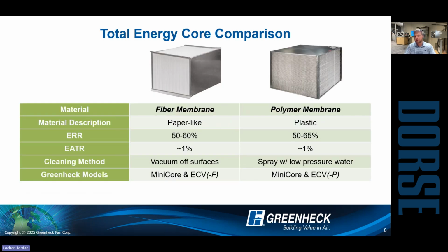On the core side of the market, right? So there's two primary core media types that are out there. A fiber core is a paper-like material, and then a polymer core, very similar to that wheel, is a plastic type media, right? That is a washable and reusable core, right? So you can see the difference there. Cleaning, one is vacuum only, one is low pressure water wash. The big difference being with cores compared to wheels is lower performance, right? So 50 to maybe 65% ERR is what can be expected. So, as you can imagine, those fiber cores are a little bit harder to hit those code minimums. So typically we like to use the polymer cores, and that's something that's slightly unique to Greenheck. A lot of the other competitors in the market are only using a fiber type core media.